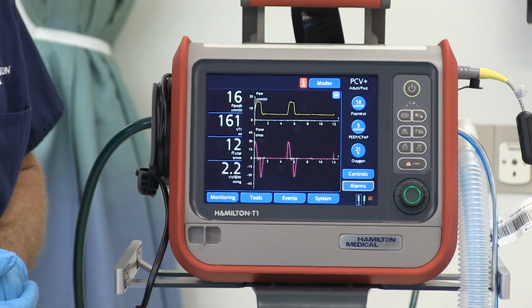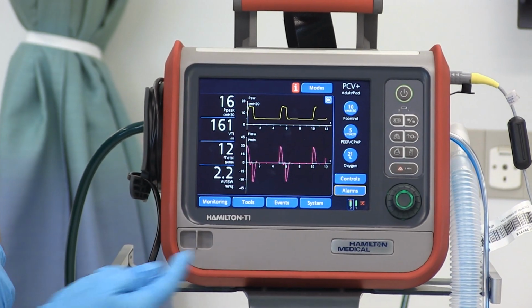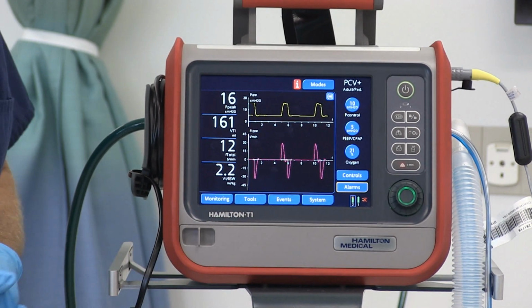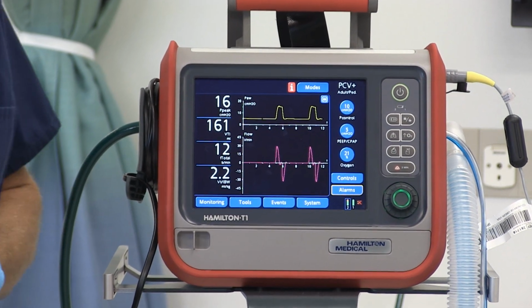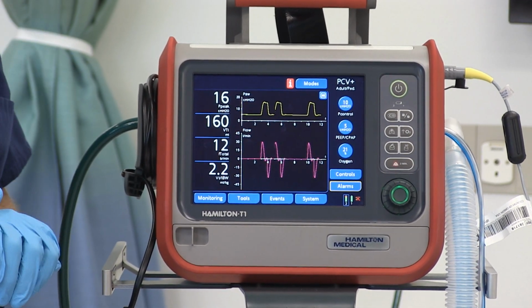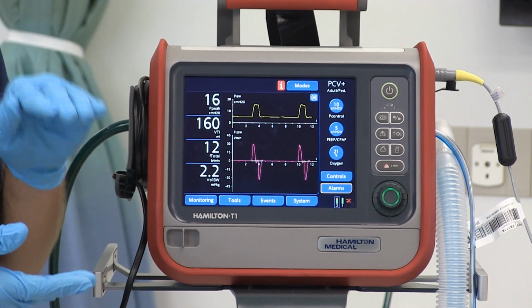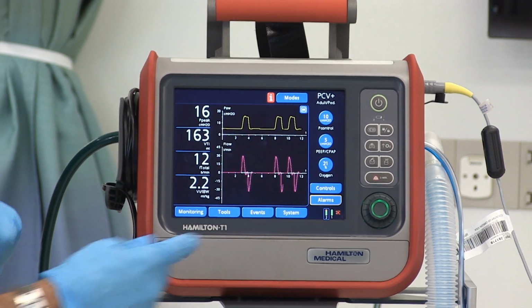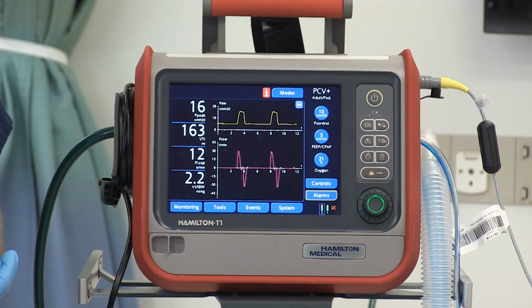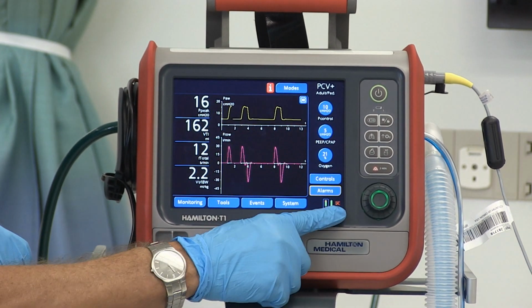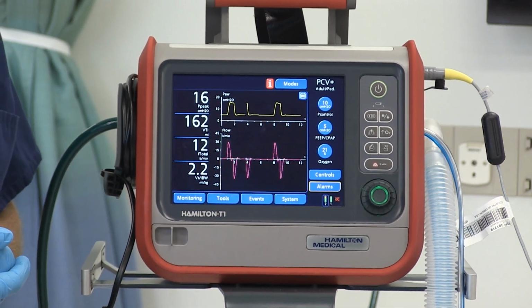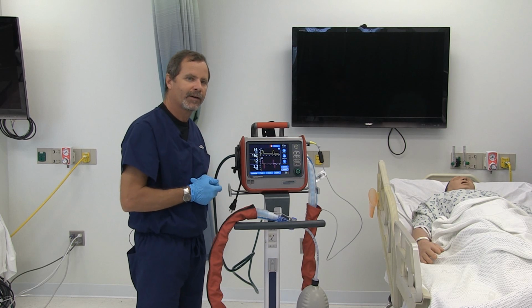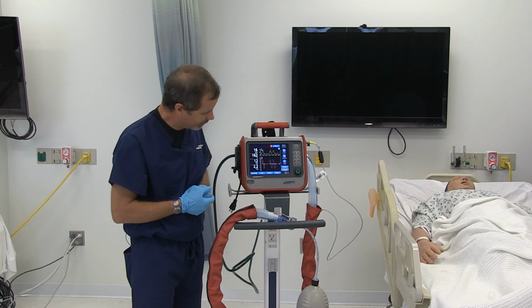Let's close that. Below there is your battery indicator, so you can see battery number 1 and battery number 2. Battery number 2 is partially depleted, you can see, because it's turning yellow from the top. So the more depleted the battery, the lower the yellow goes on the indicator. And you can see battery number 1 is fully charged. We can also see that the ventilator is not plugged in because we see a red X through the AC plug. If I were to plug in the ventilator, that red X would disappear.